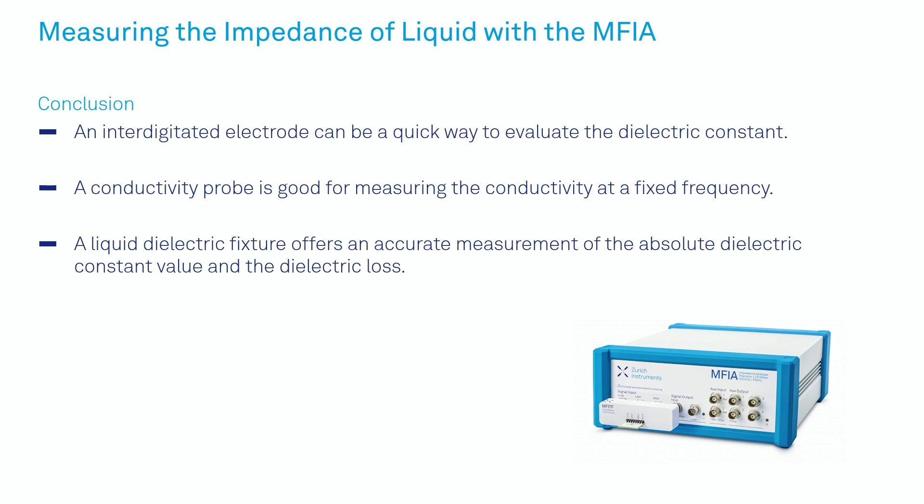An interdigitated electrode can be a quick way to evaluate the dielectric constant. A conductivity probe is good for measuring the conductivity at a fixed frequency. A liquid dielectric fixture offers an accurate measurement of the absolute dielectric constant value and the dielectric loss.